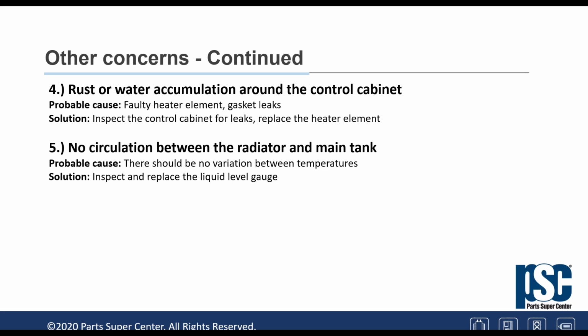Now, depending upon how many times we take an oil sample, if the tank is very small and we take a gallon of oil each sample and do not replace it, this level is going to be below the opening of the manifold. Therefore, the oil is not going to circulate, and if the oil does not circulate, it's not being cooled down. In that case, the main tank has a much hotter temperature than the radiators. That's a symptom that the oil is not circulating, and that's terrible because with no circulation, it gets hot, gets pressure, and starts blowing oil through the gaskets.